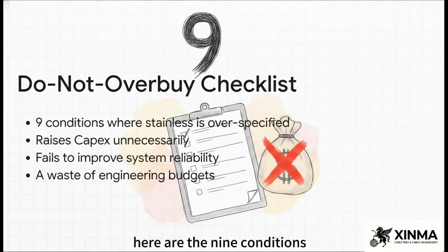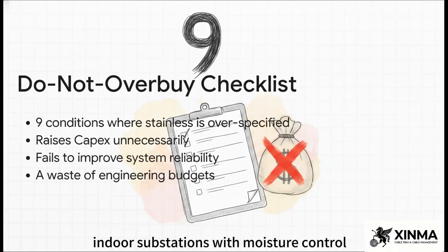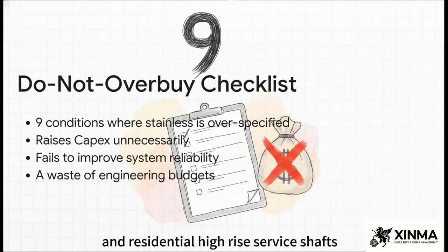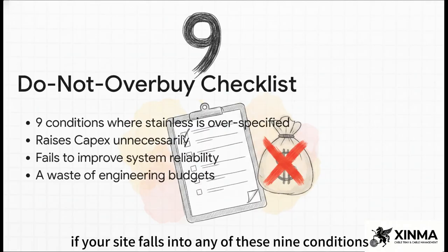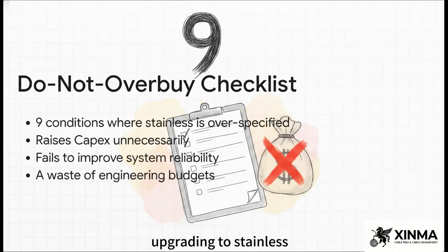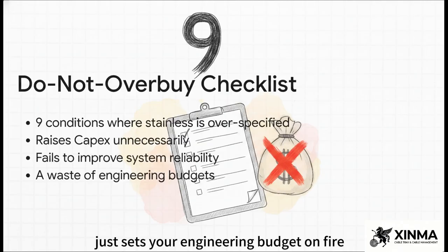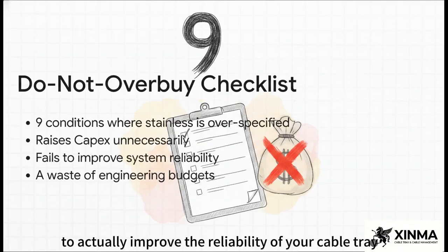Ready? Here are the 9 conditions: standard climate-controlled server rooms, typical commercial office buildings, dry underground facilities, areas with only cosmetic dust, non-corrosive manufacturing floors, standard warehouse environments, general retail spaces, indoor substations with moisture control, and residential high-rise service shafts. If your site falls into any of these 9 conditions, upgrading to stainless just sets your engineering budget on fire without doing a single thing to actually improve the reliability of your cable tray system.